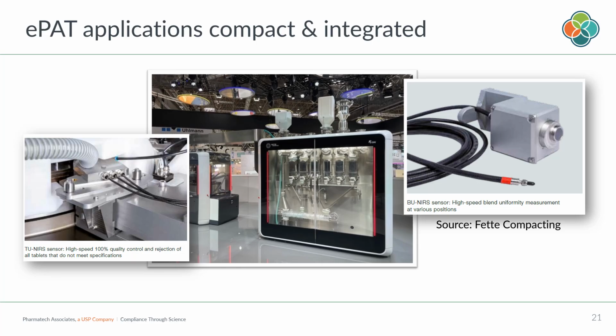So they have what they call an EPAD, an embedded tablet uniformity NIRS sensor just on top of the turret of the compression machine. They can really test 100%. It is a reflection device. So basically, because it is so fast, the compromise here is you just take the reflection of the tablet surface.